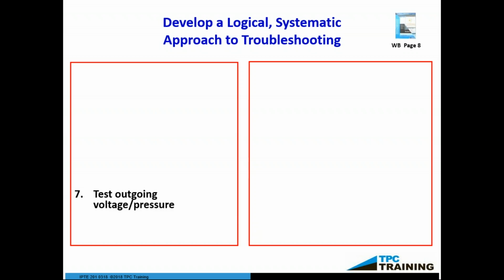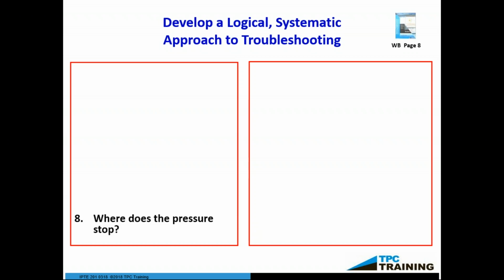Let's say pressure or voltage doesn't come out. Where does it stop? Because where it stops is a great place to start troubleshooting what's wrong with the equipment. Normally, 99% of all our failures are from something small, like a contact block or an ASCO solenoid or something like that. Once something fails, that part of the equipment is going to stop working correctly, but we have to know what that part of the equipment does in order to troubleshoot.